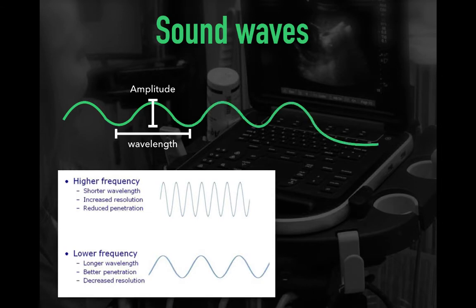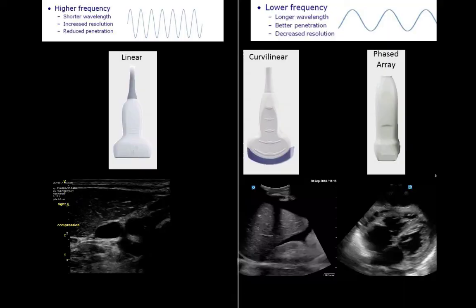Back to our sound waves. Ultrasound probes are designed to release a set frequency and wavelength — generally lower spectrum, like 2 to 4 MHz, or high, like 6 to 14 MHz, with the middle range in between. High-frequency shorter waves are great for superficial resolution but due to attenuation cannot penetrate deeply.